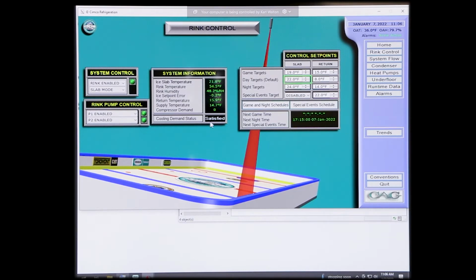We will then start. You will see this cooling demand status change from satisfied to cooling. You will run those compressors, however many it's calling for, to half a degree below set point. So at 21.5, the compressors will shut off. Okay? When you're running in return mode, it's 2 degrees above set point, 2 degrees below set point. Because return picks up temperature much faster than slab does, we give it a little bit longer span before we start bringing compressors back on again. Right? So 2 degrees above, 2 degrees below.